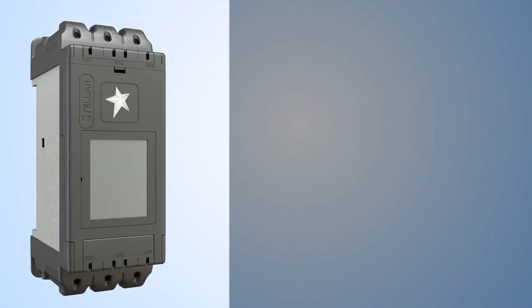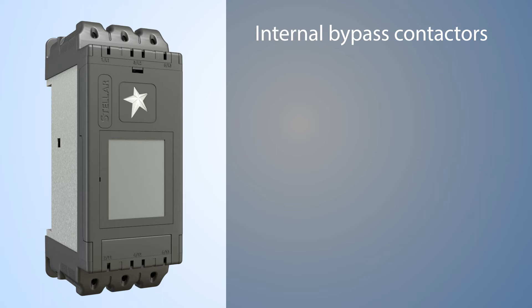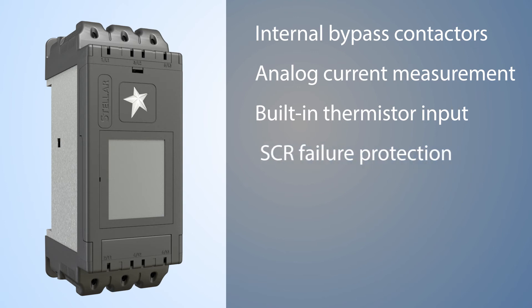Under the hood, you'll find built-in internal bypass contactors so you don't have to add them yourself. Built-in current measurement for those times when you just need one extra analog input and don't want to spend the money on adding a whole other controller. Built-in PTC thermistor input — perfect for keeping up with your motor's temperature, without having to add an entire controller just to monitor one temperature value. And built-in SCR failure protection to help ensure a long life.